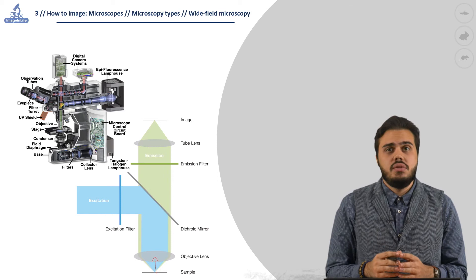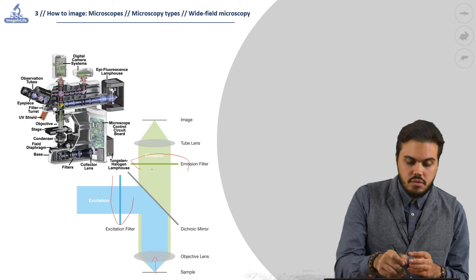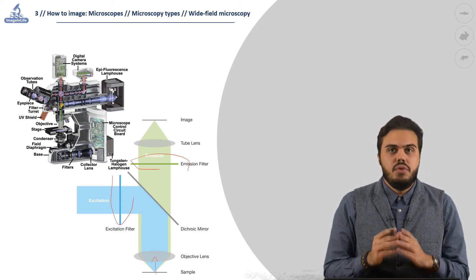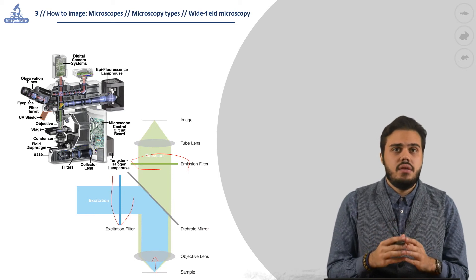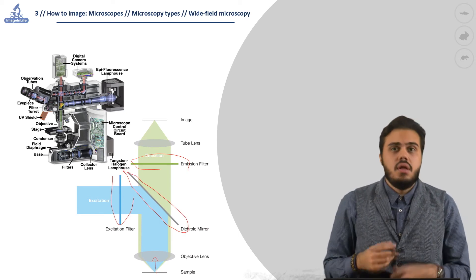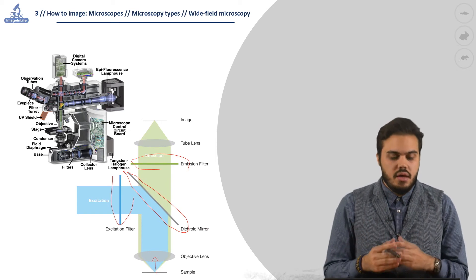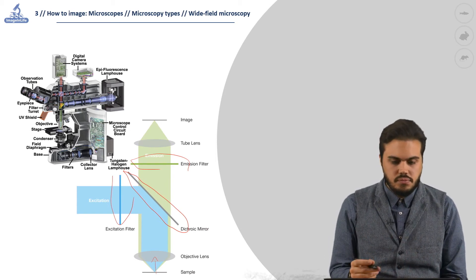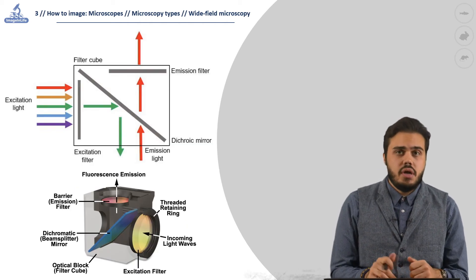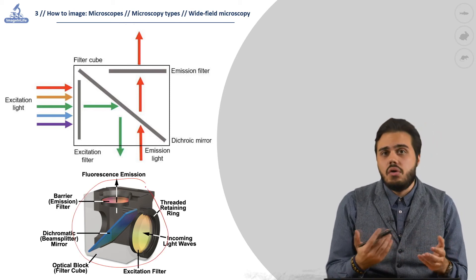The epifluorescence works thanks to the excitation and emission filters and the dichroic mirror that reflects the excitation light and lets the emission light proceed towards the camera and get acquired. Usually all these components are inserted in cubes that can be swapped based on the wavelength or color we want to observe.